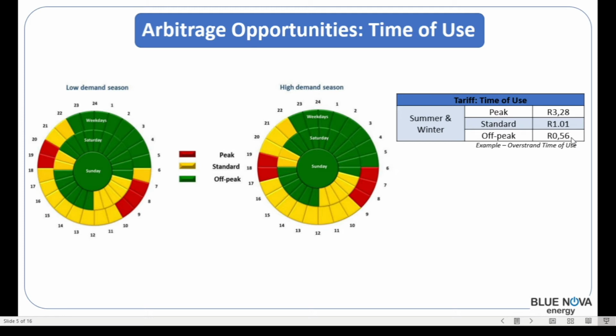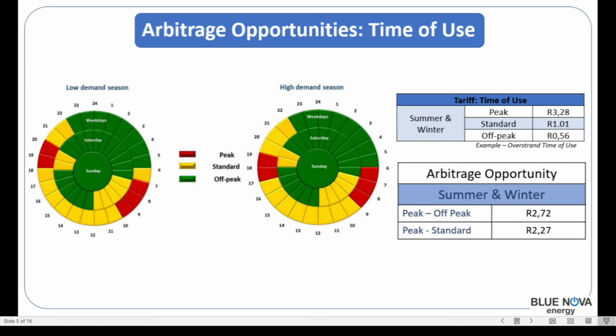So one can purchase electricity at 56 cents for a certain acquisition cost, which is the cost of owning a storage device, and then discharge that during the peak periods. One can also do that during the standard period, where you purchase electricity at R1.01 in this case, and then use it during the peak period. There's an arbitrage opportunity, before the cost of the arbitrage machine, of about R2.27. So between peak and off-peak, R2.72 opportunity, and between the peak and the standard period, R2.27.